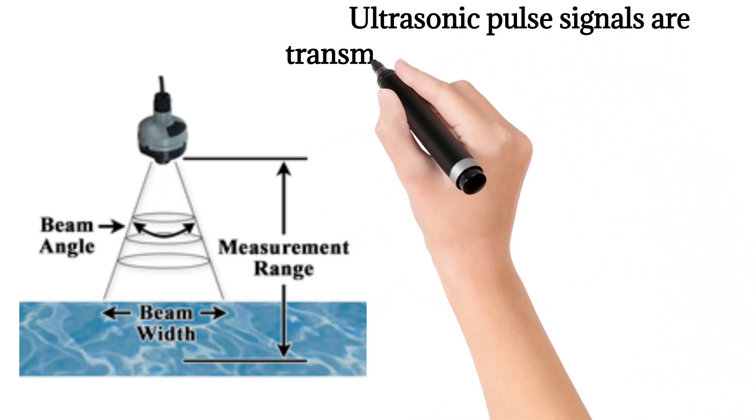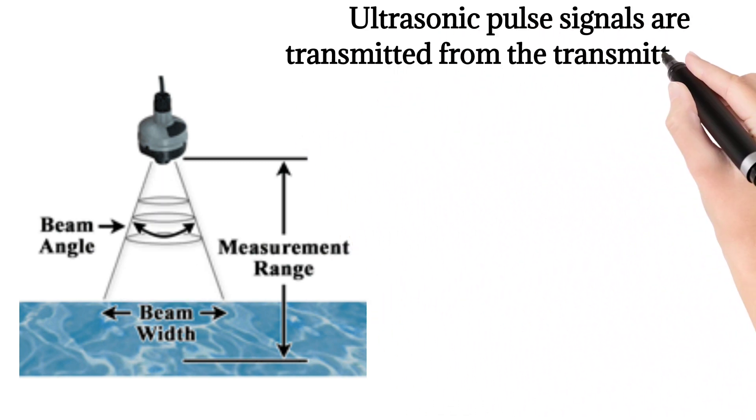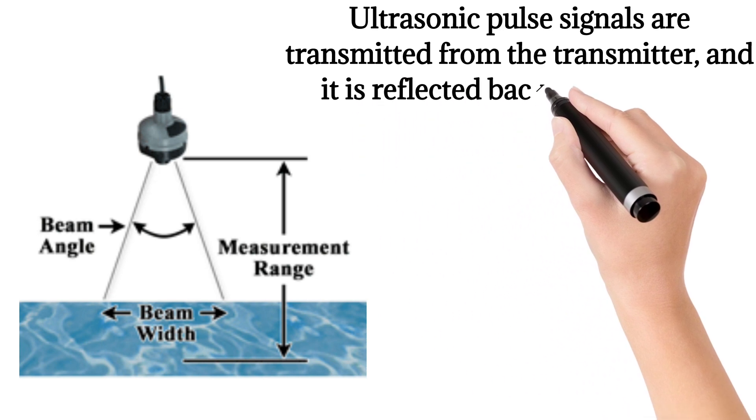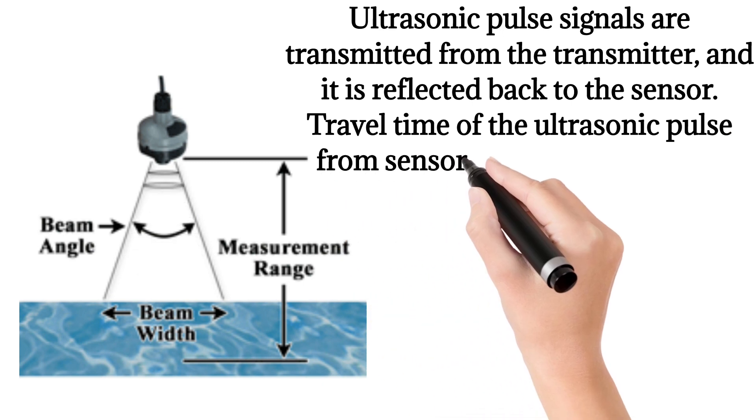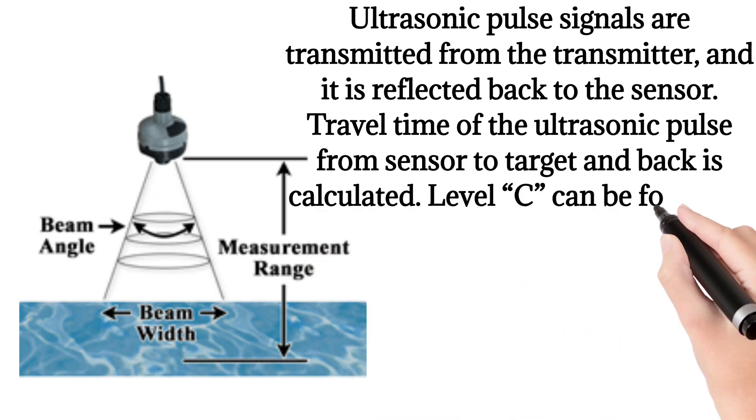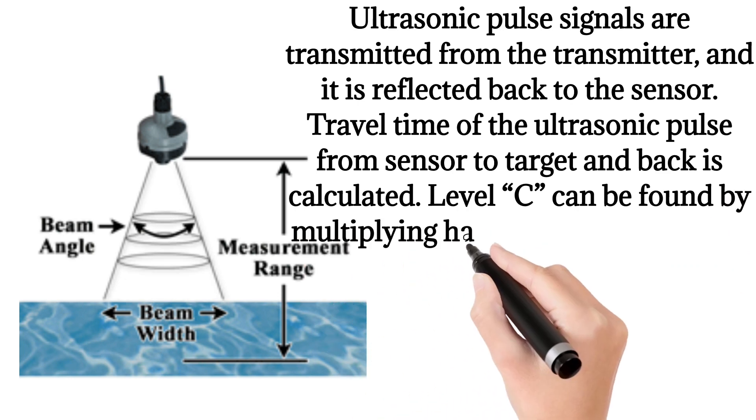Ultrasonic pulse signals are transmitted from the transmitter and reflected back to the sensor. Travel time of the ultrasonic pulse from sensor to target and back is calculated. Level C can be found by multiplying half of this time with the speed of sound in air.